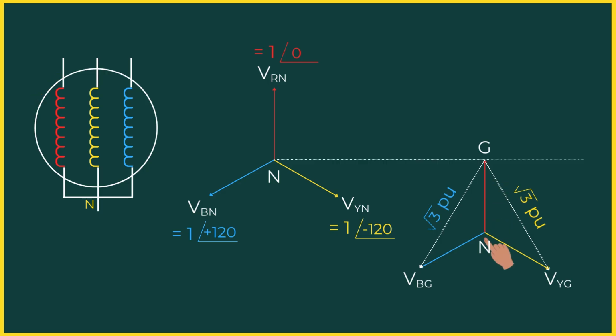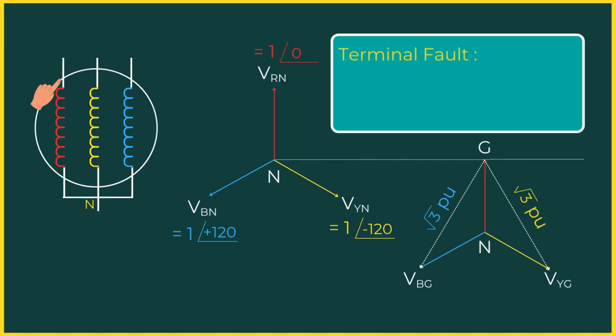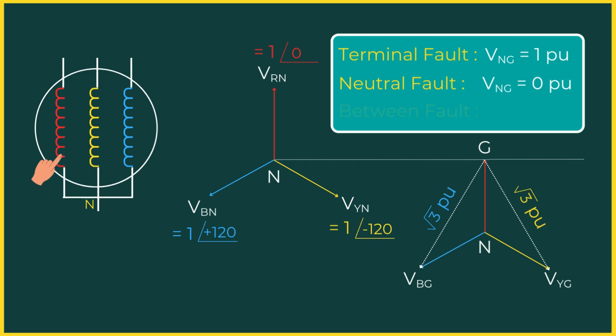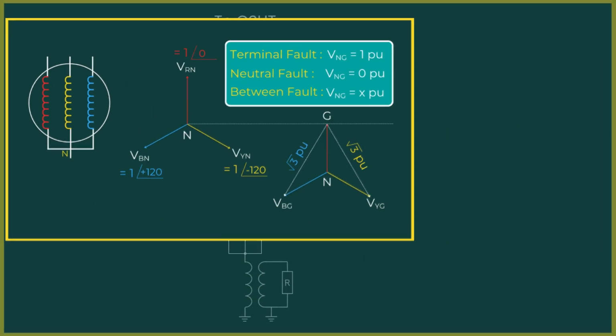The magnitude of this displacement depends on the location of the fault along the winding. Fault near the terminal, displacement is close to the full phase voltage. Fault near the neutral, displacement is very small, almost 0. Fault in between, displacement is proportional to the distance of the fault from the neutral. The protection relay measures this neutral voltage displacement to detect an earth fault. Now let's see how this is actually measured in practice.